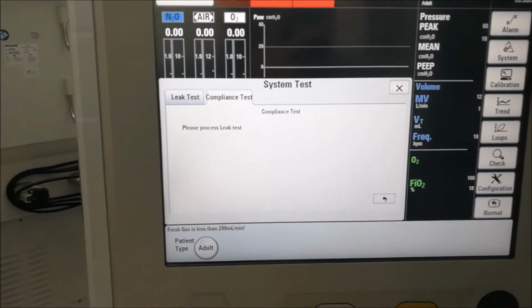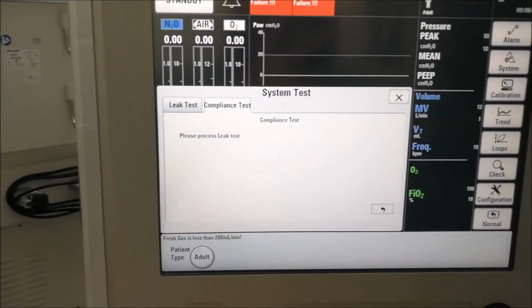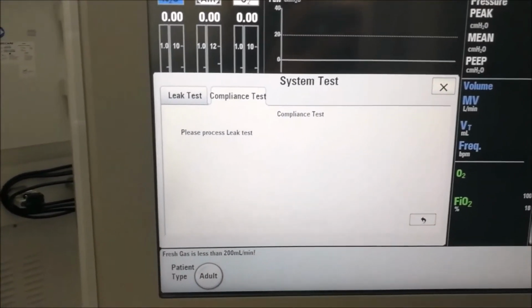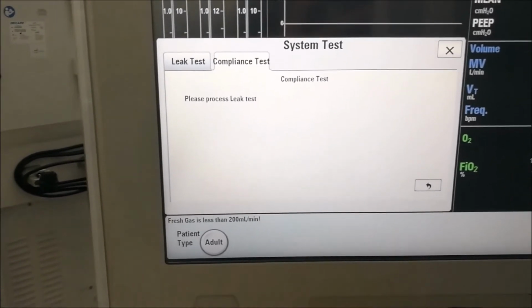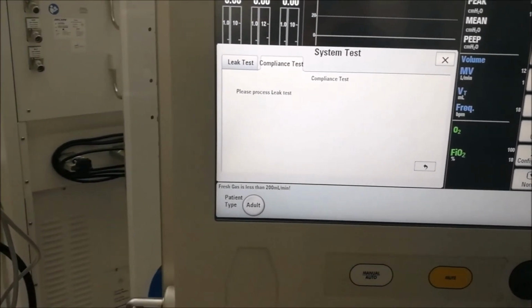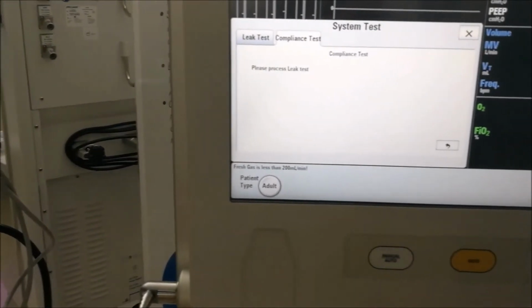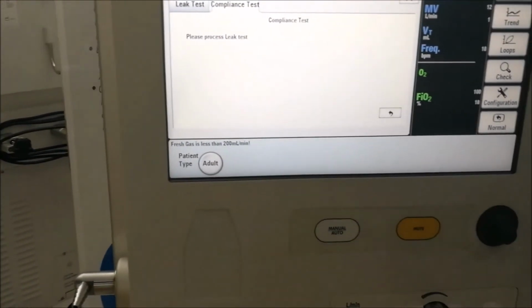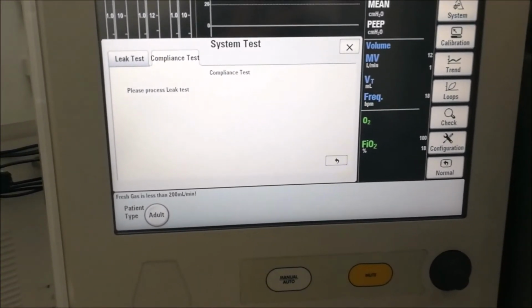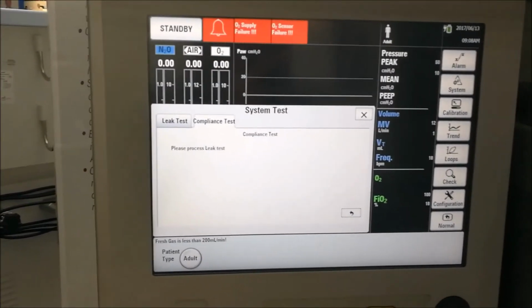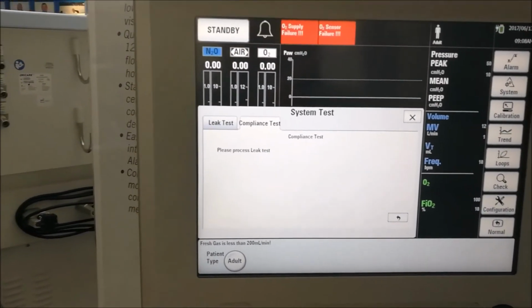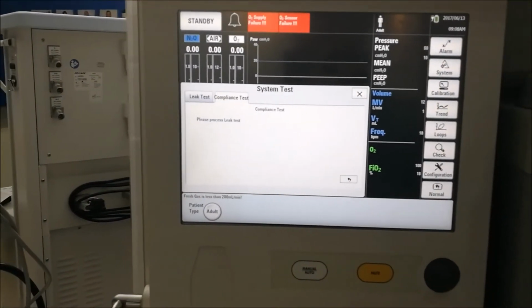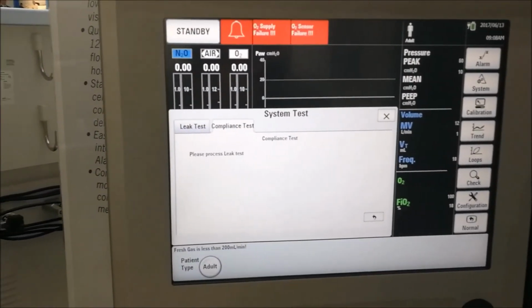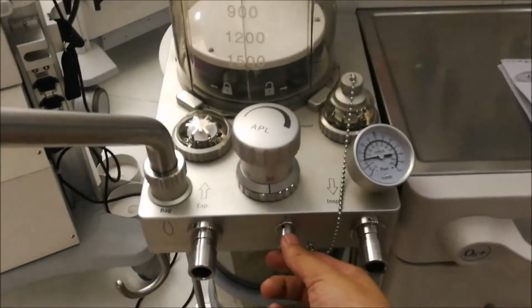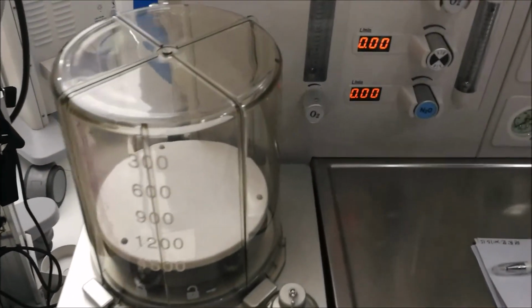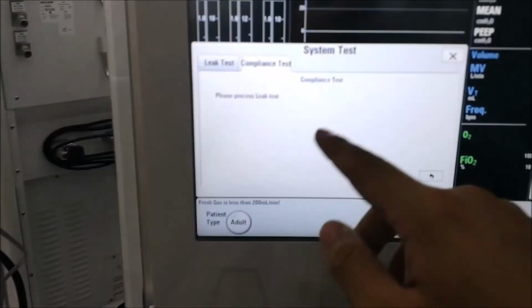Our second is the compliance test. For the compliance test, we first need to do the leakage test, and then we connect the. Now we haven't this part, so we can't do this. But if you have the gas supply, you just take the tube. The white piece, remember the white piece. You just take the white piece out, and connect the test line, and then we just do start. It's okay.